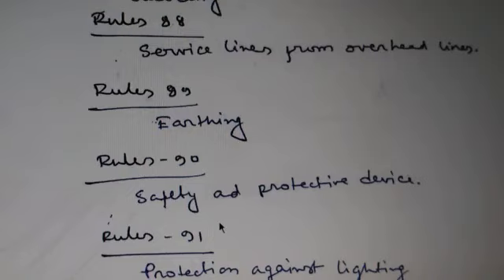Under this rule, the following points are: every overhead line erected over any part of a street or public place, or in any factory or mine or any consumer's premises, shall be protected with a device approved by the inspector for rendering the line electrically harmless in case of breakage. Next point, an inspector may, by notice in writing, require the owner of each such overhead line to protect it in the manner specified in the rules. Next, the owner of every high and extra high voltage line shall make adequate arrangement, to the satisfaction of the inspector, to prevent unauthorized persons from access to the support of such overhead lines without the aid of a ladder or special appliances.